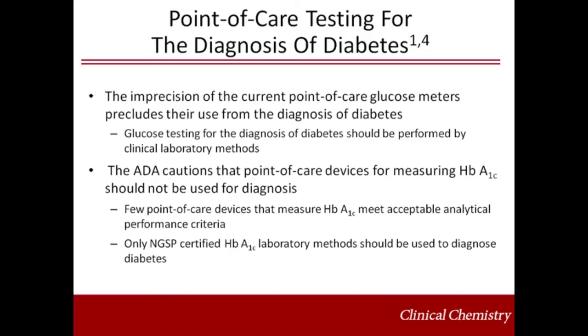Although most portable meters use whole blood and have been programmed to report a plasma glucose concentration, the imprecision of the current meters precludes their use from the diagnosis of diabetes. Although attractive because of convenience, ease, and accessibility, testing with portable glucose meters would generate many false positives and false negatives. For hemoglobin A1C, the ADA cautions that point-of-care devices for measuring hemoglobin A1C should not be used for the diagnosis of diabetes. Although several point-of-care hemoglobin A1C assays are NGSP certified, the test is waived in the United States and proficiency testing is not necessary.